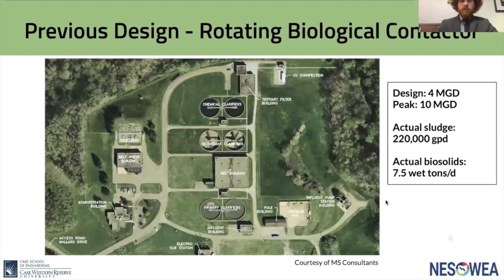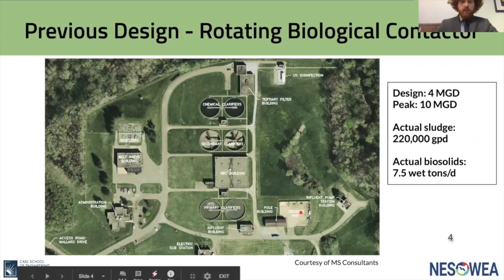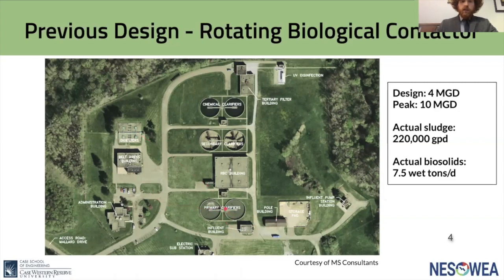The current design of the plant, as of the summer, is the rotating biological contactor plant. In this building diagram, there is an influent station which goes through primary clarifiers, which drain to the digester building. The liquid flow then goes to the RBC building, which goes to chemical clarifiers, and the sludge from those clarifiers goes to the digesters. There are two solid streams of sludge going to the digesters. The current design is for 4 million gallons per day with a peak hydraulic capacity of 10 million gallons per day.